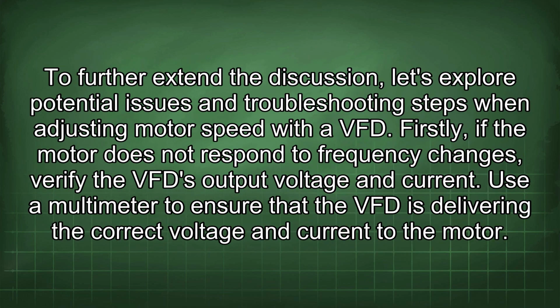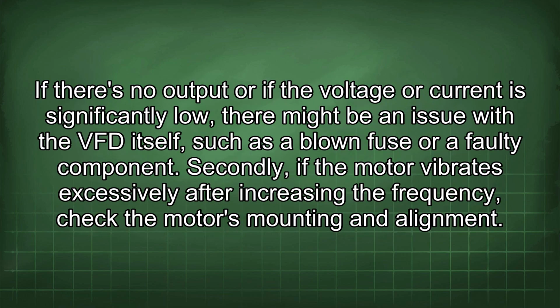To further extend the discussion, let's explore potential issues and troubleshooting steps when adjusting motor speed with a VFD. Firstly, if the motor does not respond to frequency changes, verify the VFD output voltage and current. Use a multimeter to ensure that the VFD is delivering the correct voltage and current to the motor. If there's no output, or if the voltage or current is significantly low, there might be an issue with the VFD itself, such as a blown fuse or a faulty component.